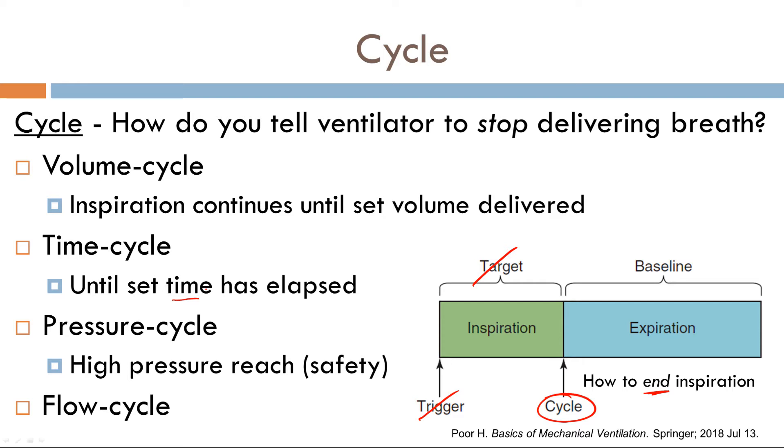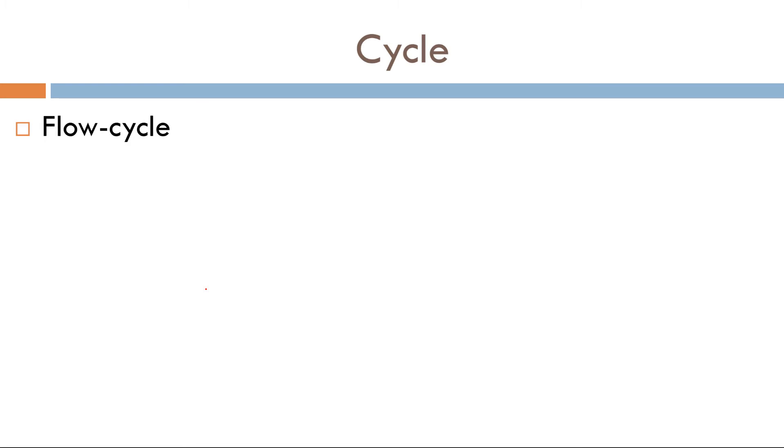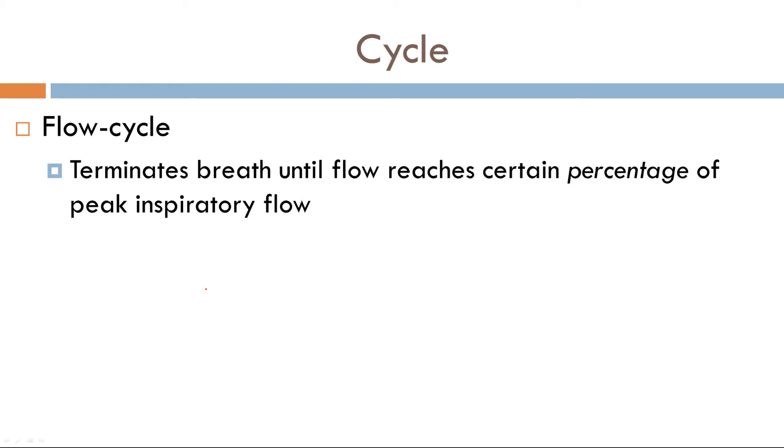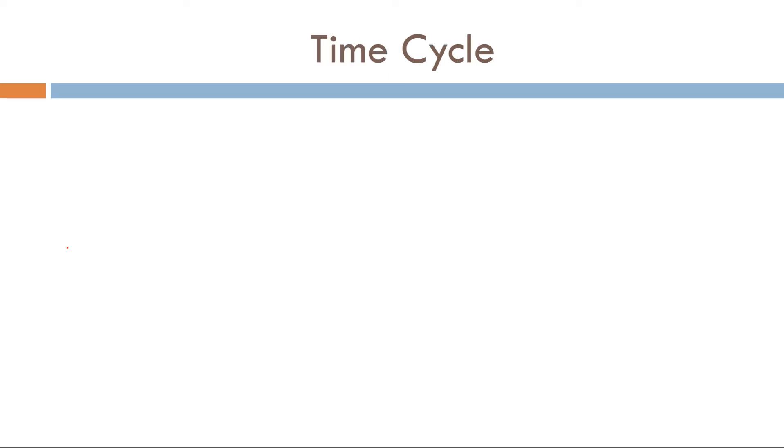And finally is flow cycle. Now flow cycle is conceptually the most difficult to understand, so I'll define it, but we'll go in depth in it in a bit. Flow cycle terminates a breath until the flow reaches a certain percentage of the peak inspiratory flow.